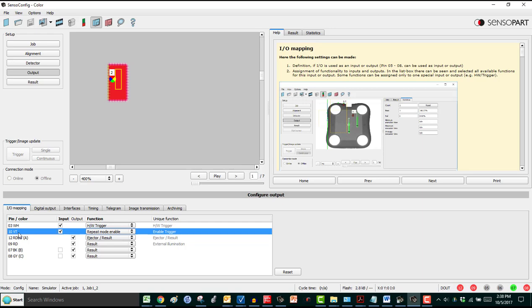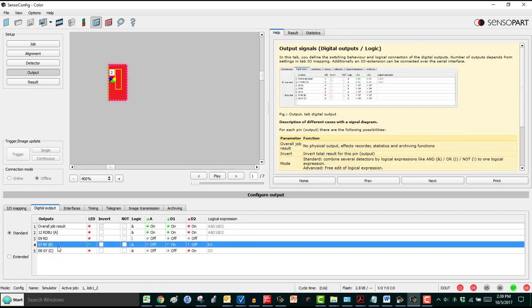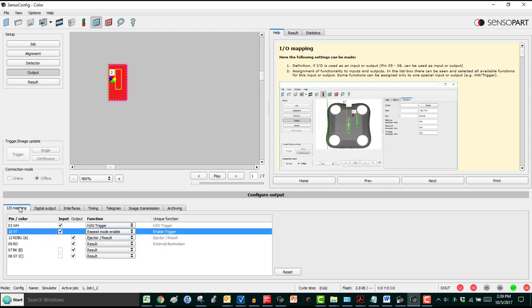So when the 4x4 palette is in front of the photo eye, its output will be on. And repeat mode means the camera will keep triggering itself repeatedly until it gets a result. So once it gets one of these results, the camera will stop triggering itself, the light will stop flashing, until it sees the next palette.